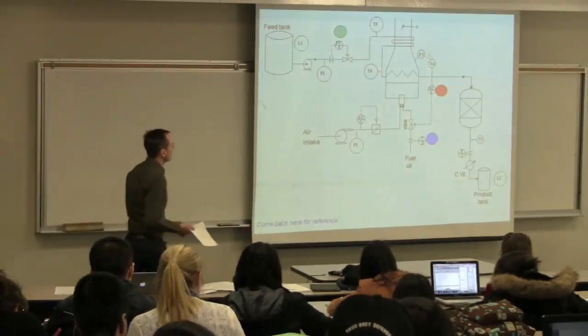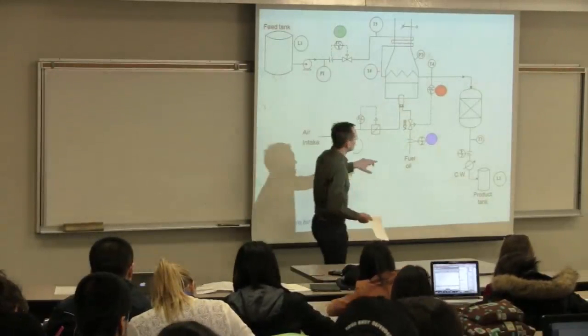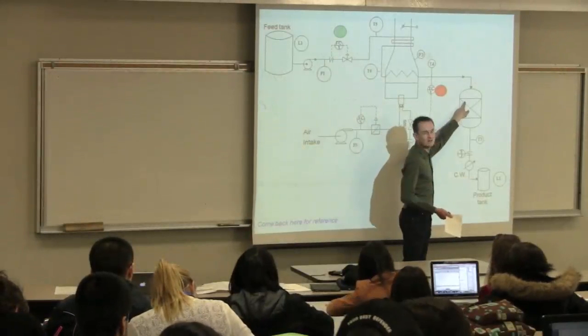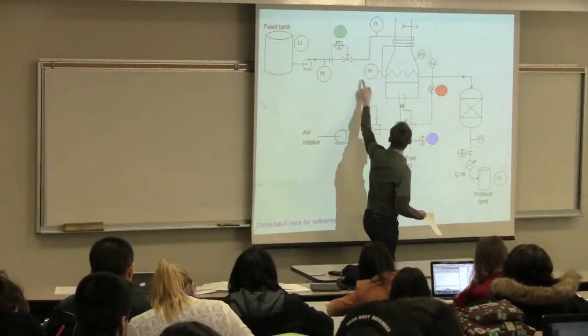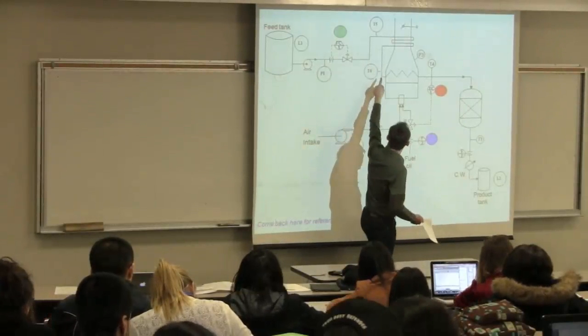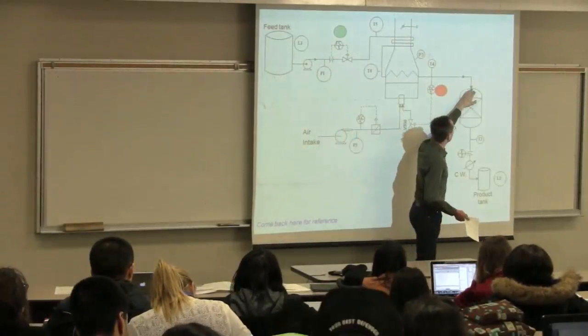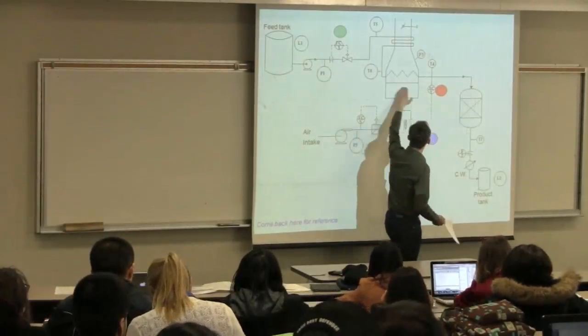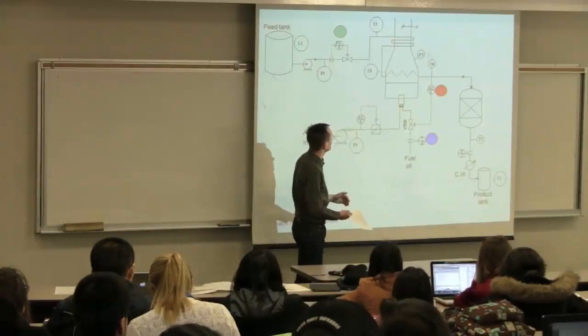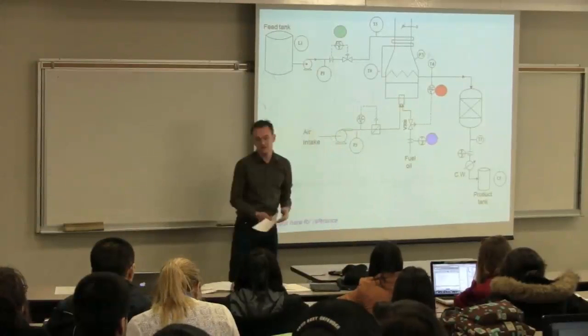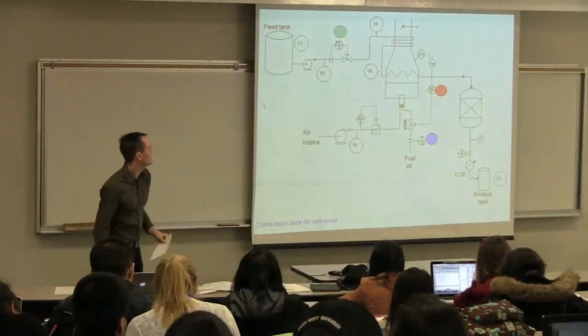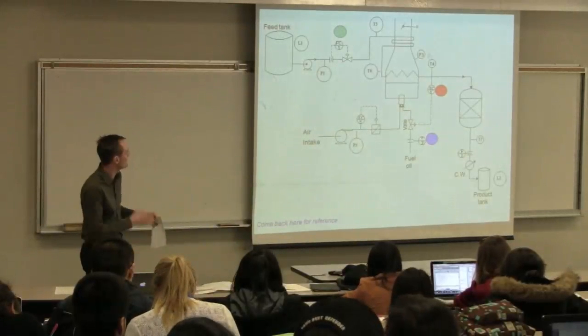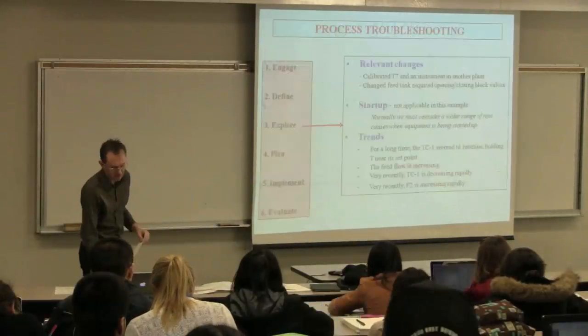Another root cause you might think is, well, something's got plugged up in this packed bed. Because I'm increasing the feed flow over here, but if this packed bed is plugged up, essentially less fuel is getting to it, and I'm accumulating some material in there. And so that temperature is dropping. I'm essentially getting lower flow through the system. I'm seeing this transient behavior.